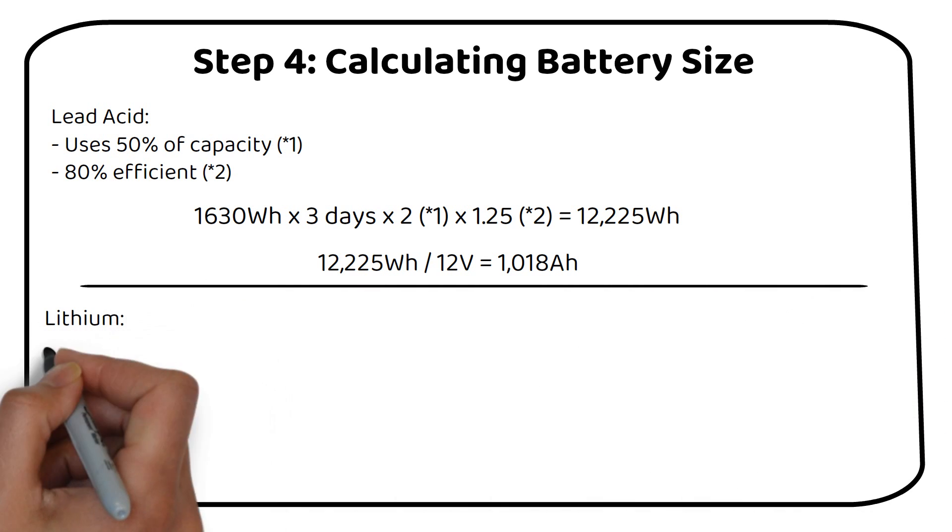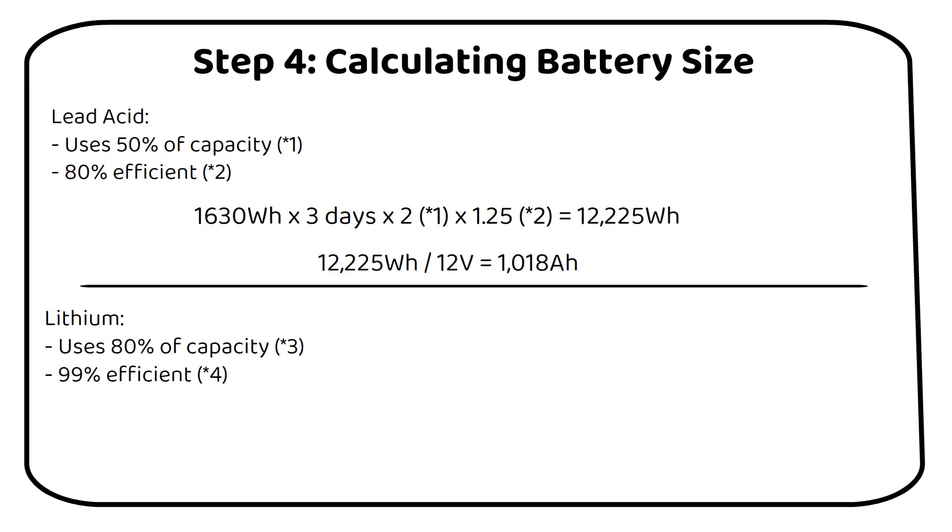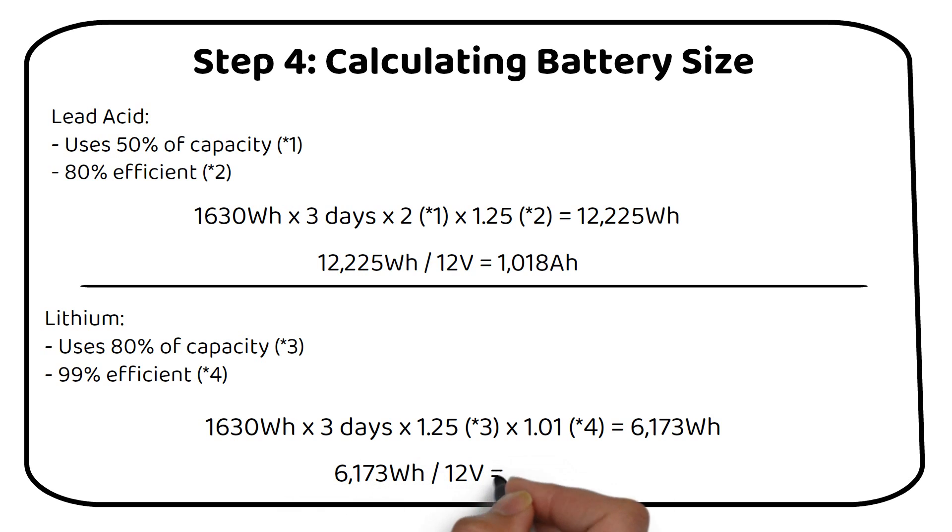For lithium batteries, the scenario is more favorable. You can use up to 80% of a lithium battery's capacity. And they boast a higher energy conversion efficiency of 99%. Applying the same load analysis, we get 1630Wh, which is the daily usage, times 3, equals the days of autonomy, times 1.25 equals 80% usage, times 1.01 equals 99% efficiency, and we become 6173Wh. Dividing this by the battery voltage gives us 6173Wh divided by 12V equals 514Ah. This comparison clearly shows that lithium batteries require a much smaller capacity than lead-acid batteries for the same energy needs, thanks to their higher efficiency and greater usable capacity.